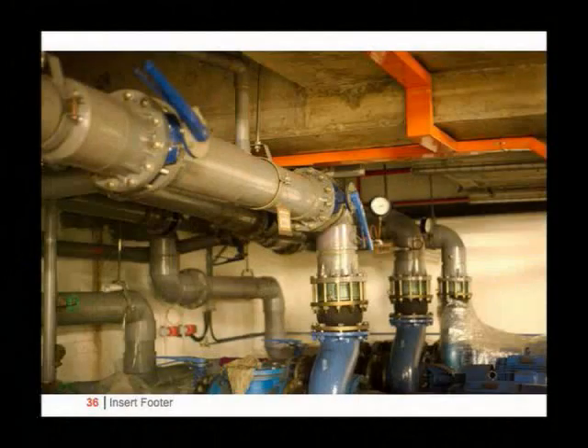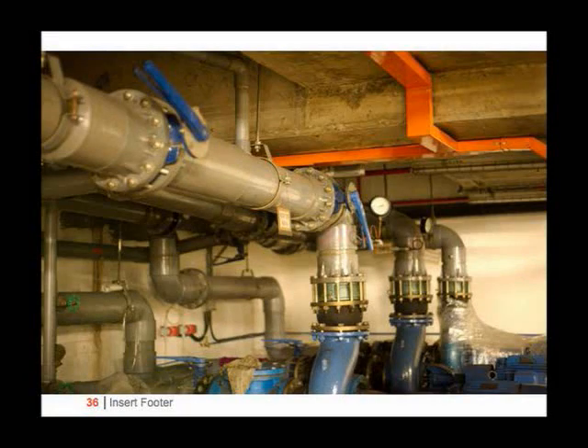And if you look at the piping design, this is a very short radius elbow, which is not what you need. And on the suction side, one has the same problem. Everywhere there are right angles. And just in case the first throttling valve was not enough, which it wasn't, they put a second one. So we are not talking rocket science. There's a lot of common sense that seems to disappear in the real world. Look at the number of right angle elbows everywhere.